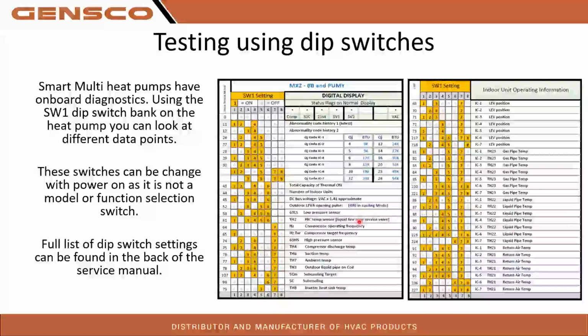So if you're seeing that 7102 error code, I'd be looking at indoor units connected. Make sure it shows all the indoor units that you have, or however many of them you do have. If it does show that, start looking at these capacity codes. If one's reading 0 or one's reading 50, but there's something connected there, it could be a power supply issue or a communication problem. Or in the example of a cross port, if I know ports A, B, and C are a 9, 12, and a 6, and I look and port A is not a 9, it's actually the 12, what's going on here? Then I know that system is probably cross-wired. If we know our line sets are connected up but our wires are reporting the sizing wrong, that's another handy tool you can use.